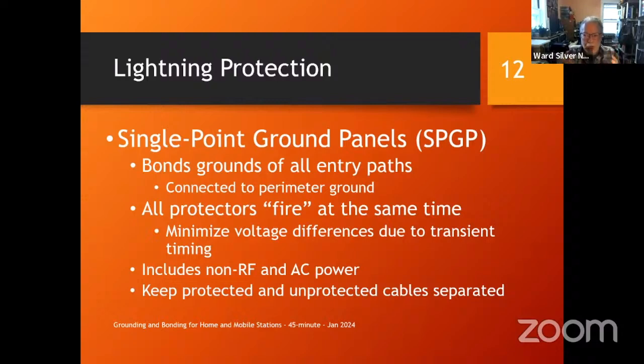And when you fire at the same time, that minimizes the voltage difference. You don't want one protector way over here and another protector way over there, because that creates big transient voltages between different parts of your system. And those can be multiple kilovolts. It doesn't take very long for a multiple kilovolt electrical pulse to generate a lot of destructive current. It just takes microseconds. So you want all of your protectors together so that they fire at the same time. And that's not just your lightning protectors for your coax.